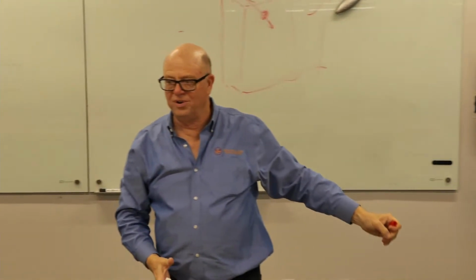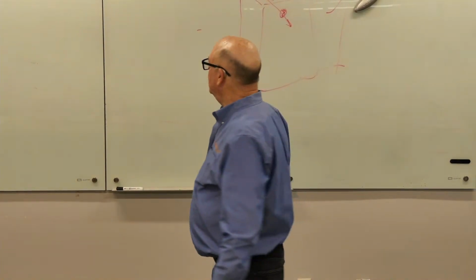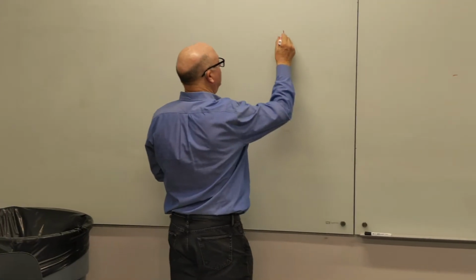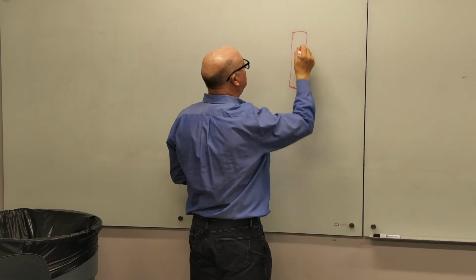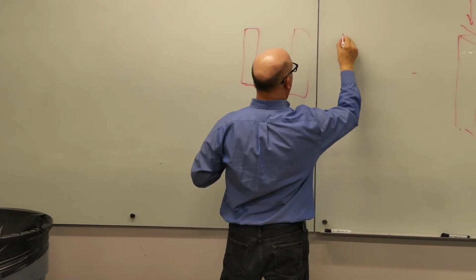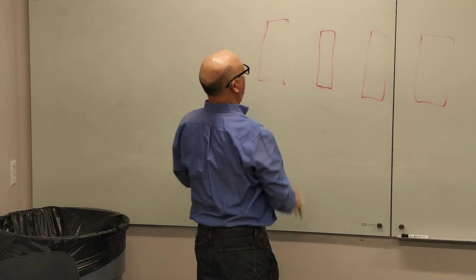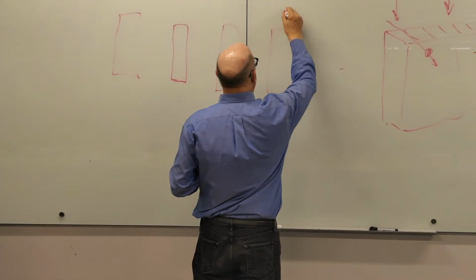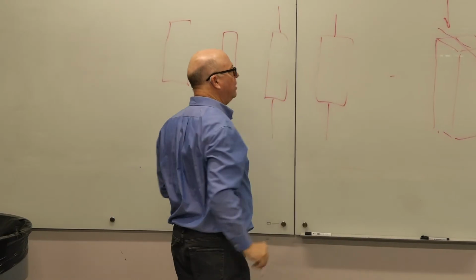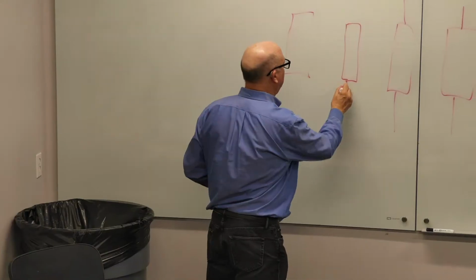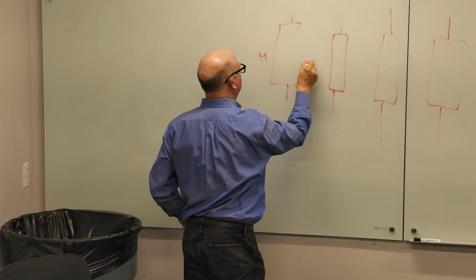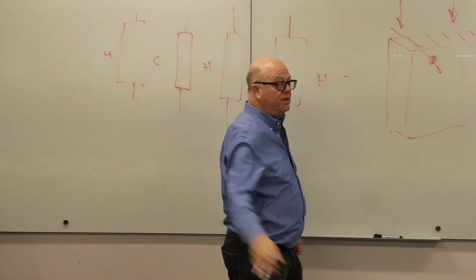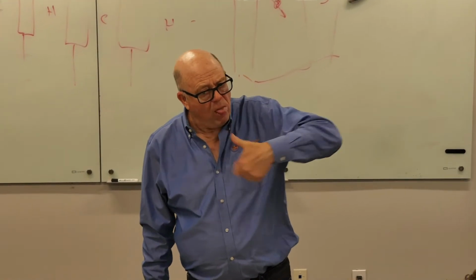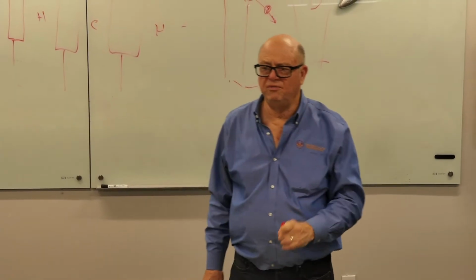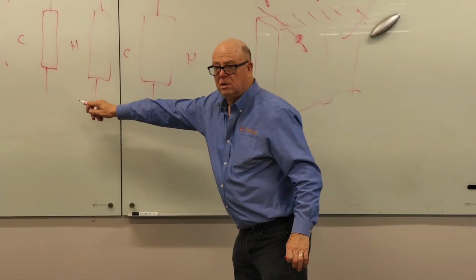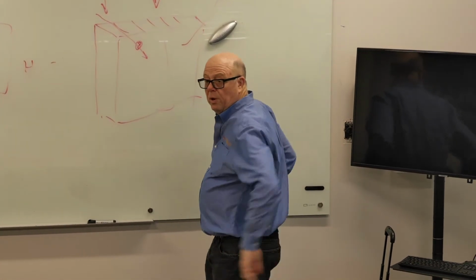And if you had yet another row, what did you have to do? You had to put up walls. Because this is what you end up doing in an old style. There's still a lot of these that don't do any more than that. You could improve the efficiency if this is plan view, and I've got a bunch of server racks. If I create a wall, and hell, it could be anything to prevent air movement. It could even be plastic. If I create walls, I could make hot, cold, hot, cold, hot, and I duct it appropriately. The rule of thumb efficiency difference is between 15 and 20% if you do this versus simply dumping it in here, letting the muffin fans blow it, and then sucking it out on this side.